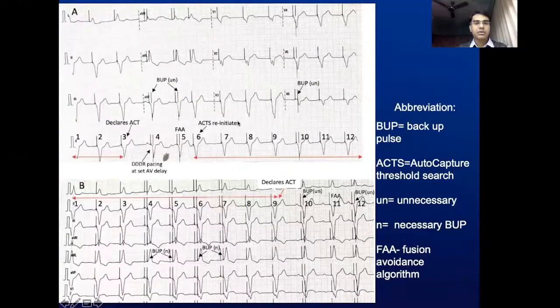So coming to our own case, what we feel is that these 3 beats were due to auto capture threshold testing, and at this third beat in the upper panel, there is a declaration of the auto capture threshold, whatever it may be. After that, 0.25 is added to that threshold, and the pacemaker function shall start with a set AV delay, which it starts here.